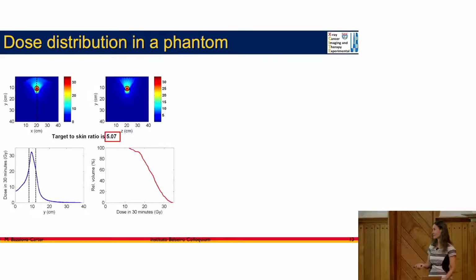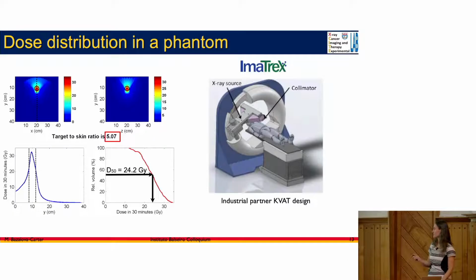And this was just done on phantoms. And the D50 was 24.2 gray and was supposed to be 18. So we are getting even higher output than we were asked. So it was exciting. However, this is just a dose distribution in a phantom. And unfortunately, humans don't tend to be cylindrical with spherical tumors. So we had to look at treatment planning, but we also started a collaboration with Imatrex. So Imatrex agreed to invest some money into this project and started building a prototype of the machine based on the design that we gave them.